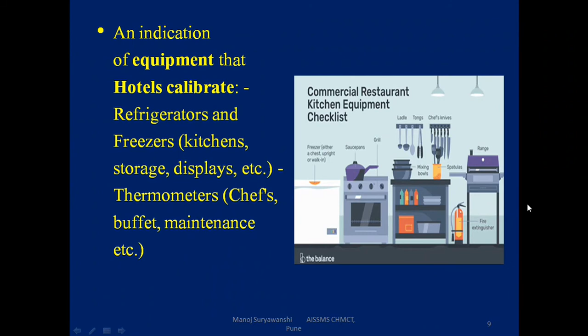An indication of equipment that hotels calibrate: there are various equipment like refrigerators, freezers, kitchen storage, displays, thermometers, chef's buffet maintenance, and so on. Each and every equipment has certain kinds of calibration process, and all the experts come from certified companies like ISO. They verify accuracy with their calibration equipments, and you can rectify the faults, because of that fault you might go for wrong weighing of the material or a wrong making process of the product, which depends on certain temperatures and certain weight. So that is why hotel equipment should be calibrated after every interval.